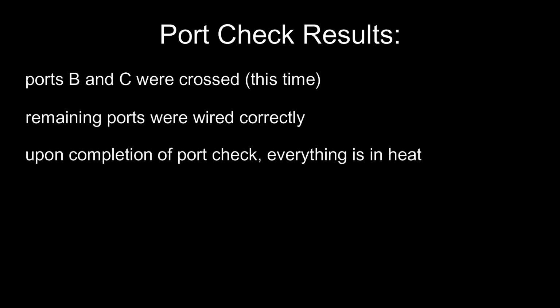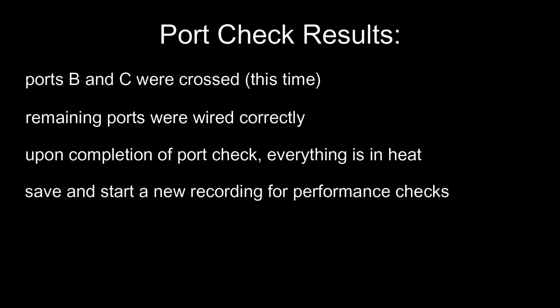saved my recording and now I'm going to go ahead and start a new file to begin my performance testing, and we're going to start in the heat mode since the system is already in the heat mode. You certainly don't have to start a new file. I just like to keep my port checks and my performance tests separate. In case I need to go back later to review something, I have less data overall to review because I've separated it all into different batches based on what I've been doing.